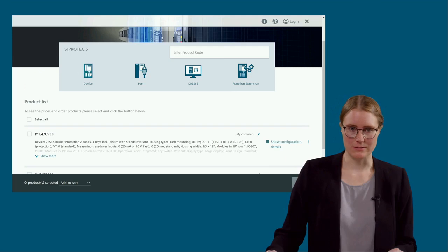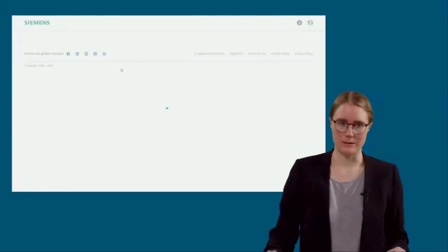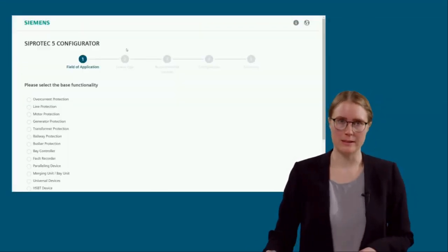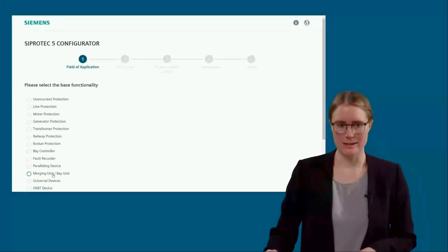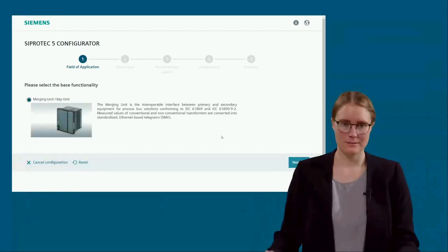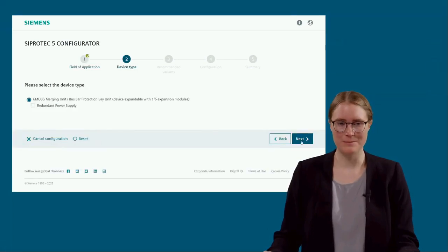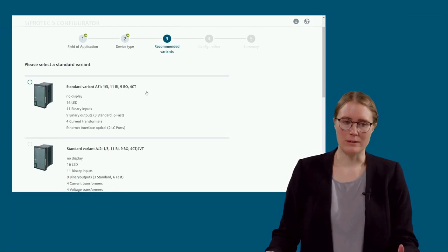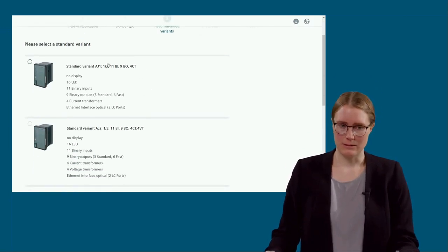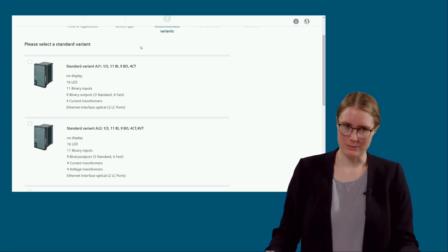Okay, so for the distributed solution, we of course need merging units as well. And this is what I want to do right now: the merging units for our IEC 61850 compliant distributed busbar protection. So this time I select merging units here. Jump over the description. And here are also some hardware variants offered. Of course, they differ in the number of binary inputs and outputs and voltage transformers. I go with the standard variant AJ1, and this is comparable to the 7SS525.